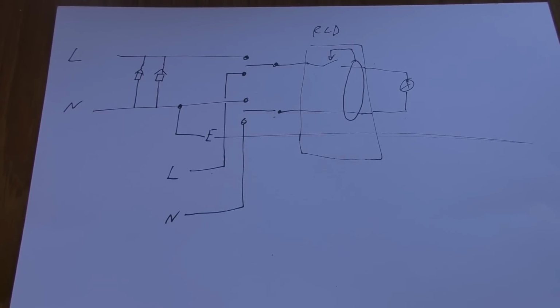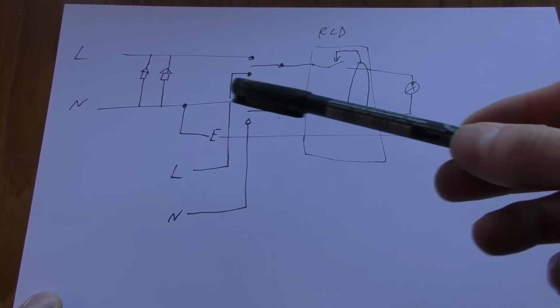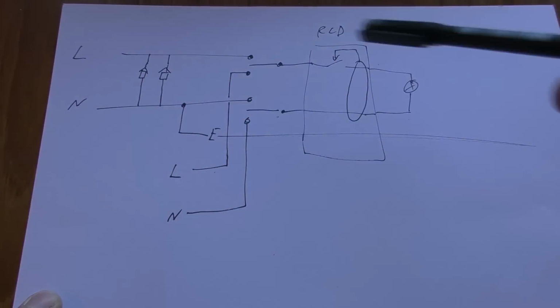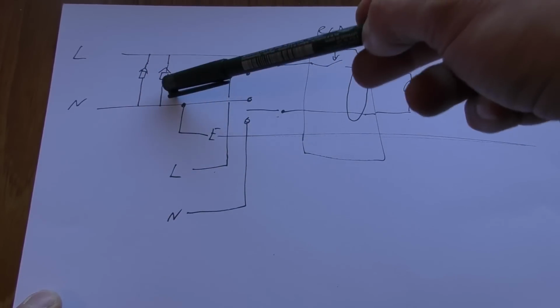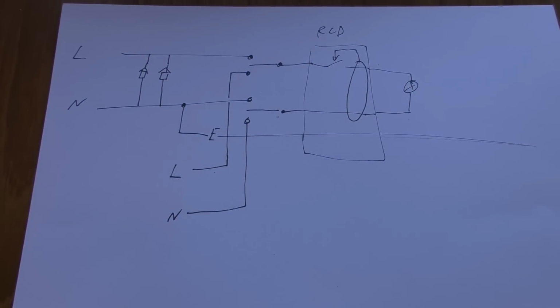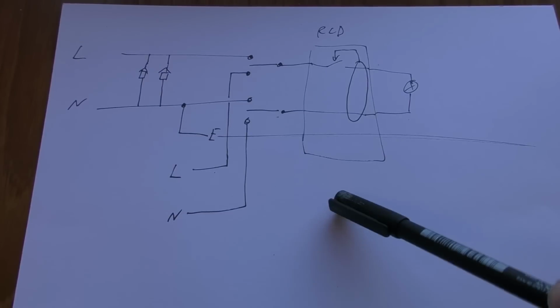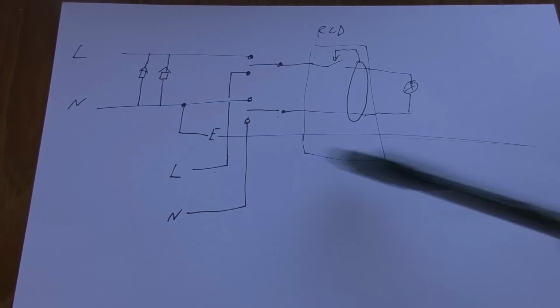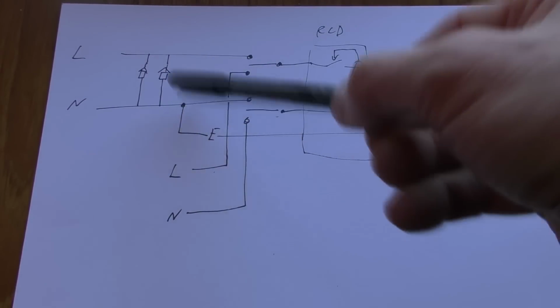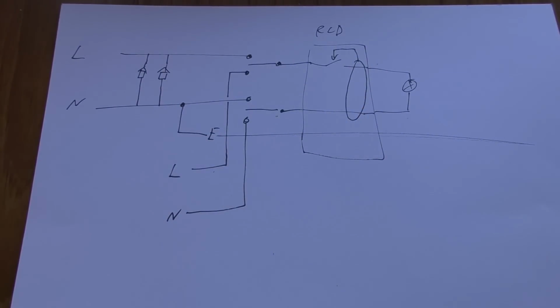Okay, now there is a subtle complication to all this, which the more you think about it, the more complicated it gets. In practice, if you're only using this for occasional use, statistically it's very unlikely to be an issue. But this is basically the situation we've got. We've got incoming grid line and neutral. We've got other houses in the street potentially connected across there, and the normal earthing arrangement in the UK is called TN-C-S, where the earth that's distributed around the house is actually connected to the neutral at the point where it comes into the house. Now mine's actually not like that, but it's probably the most common situation.